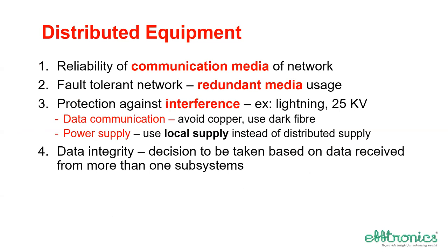Now, distributed equipment. Given their nature, the reliability of the communication media of the network plays a very big role in distributed processor-based equipment. So fault-tolerant networks with redundant media shall be used: instead of one media, two media, OFC (optic fiber) and copper cable. Then protection against interference, because it is vulnerable now as all its assets are outside and distributed, exposed to lightning and the 25 kilovolt supply. So for data communication, we should normally use dark fiber, avoid copper, and as far as possible use local power supply instead of distributed supply. There are pros and cons for power supply. We can discuss also later.